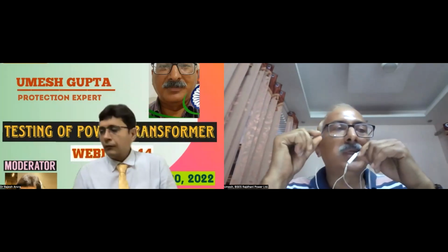Please. In a few cases, Mittal sahab, we have seen a different kind of thing also. In some cases where the transformer is more than say 10, 12, 20 years old, some damage on the core insulation has taken place, and because of the moisture inside the transformer, local heating of the core takes place, and because of that, oxidation or some gas formation takes place. It may be hydrogen or something else that flows out of the transformer and comes to the Buchholz.